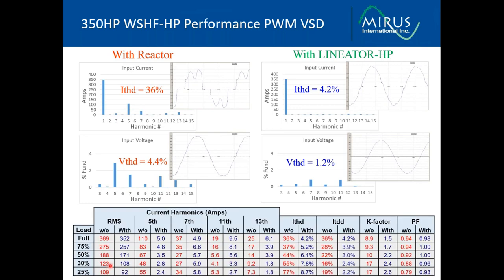The table here shows measurements taken at various load levels from 25% all the way up to full load. The RMS values of the currents, the reduction in fifth harmonic. So at full load, we went from 110 amps to 5 amps. Seventh harmonic went from 37 down to 4.9. 11th from 19 to 9.5 and so on. So the full spectrum of harmonics were reduced. THD went from 36 to 4.2.